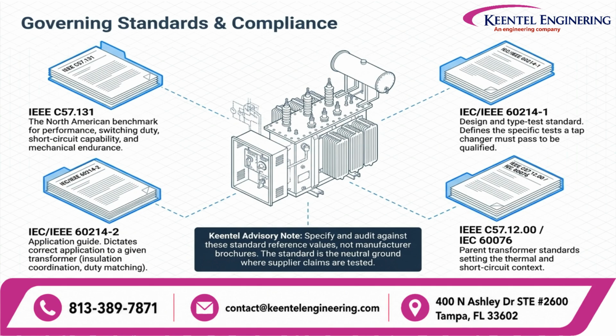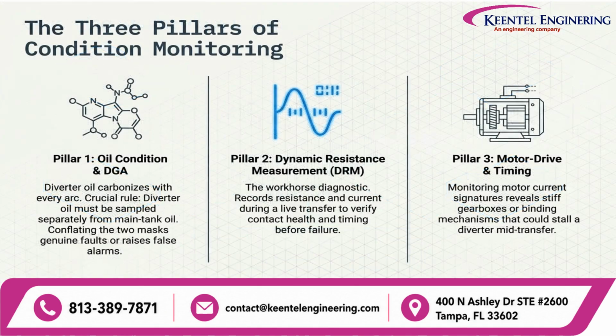Utilities often supplement these international standards with internal maintenance procedures and reliability programs. Compliance with these standards ensures equipment interoperability, operational safety, long service life, and consistent engineering quality across power systems worldwide. Modern transformer maintenance relies on condition-based monitoring rather than fixed maintenance intervals. The first pillar is oil diagnostics, particularly dissolved gas analysis. This detects internal faults by measuring gases generated from overheating and electrical discharge.